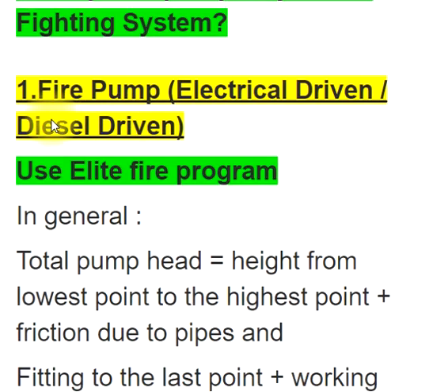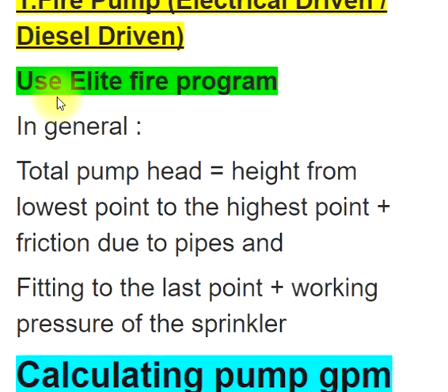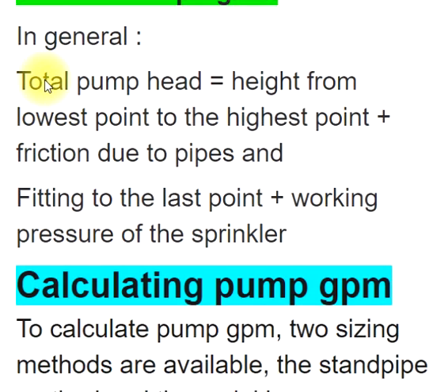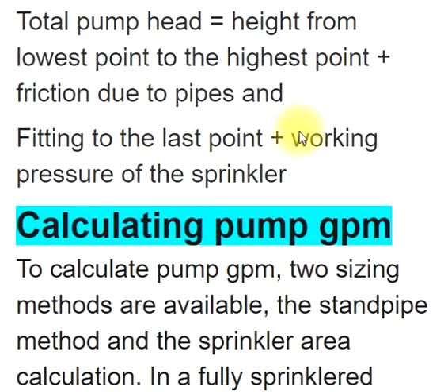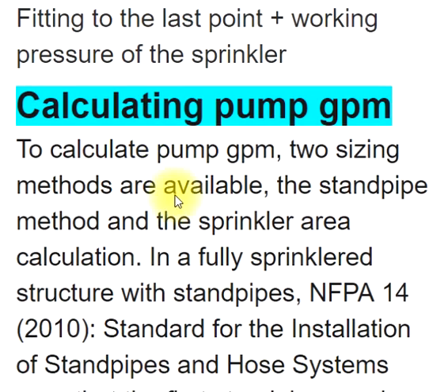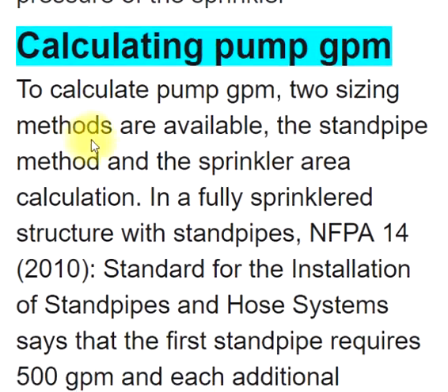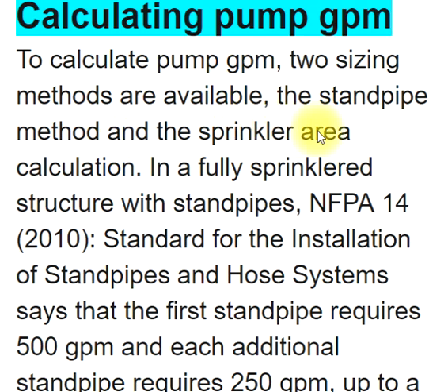Fire Pump — electrical driven or diesel driven. In general, total pump head equals the height from the lowest point to the highest point, plus friction due to pipes, fittings to the last point, and working pressure of the sprinkler. To calculate pump GPM, two sizing methods are available: the standpipe method and the sprinkler area calculation.